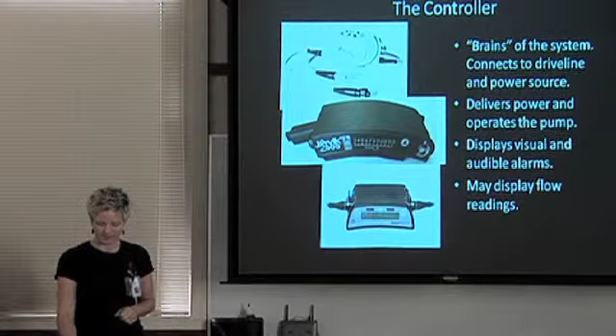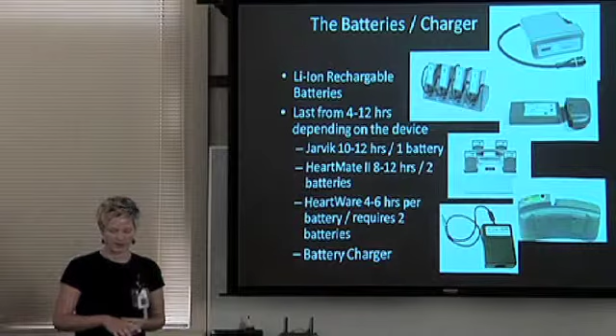The batteries: everybody has to be plugged either into the wall through AC power or on batteries. There are lithium-ion rechargeable batteries. Depending on the device you receive, they last from 4 to 12 hours. For example, the Jarvik is 8 to 12 hours on one battery. HeartMate 2 is 8 to 12 hours on 2 batteries. HeartWare is 4 to 6 hours per battery. And of course, there's a battery charger that they all plug into at night.